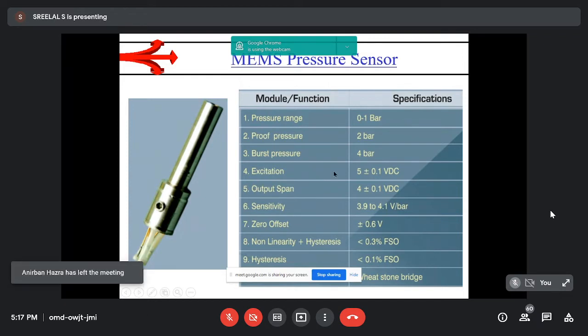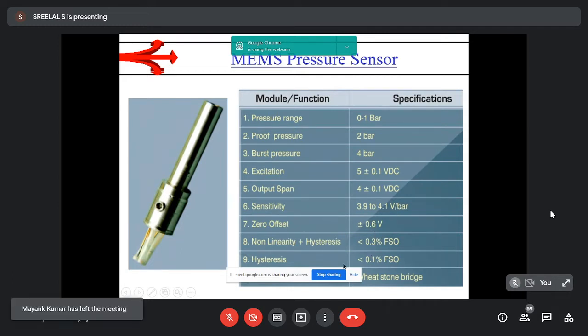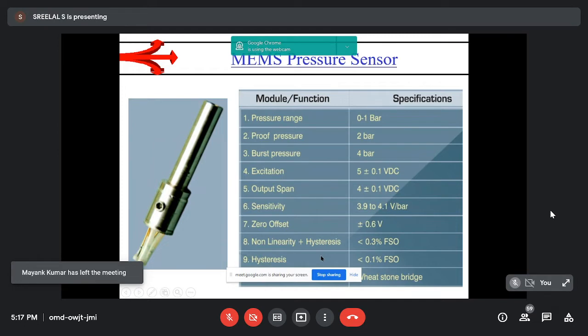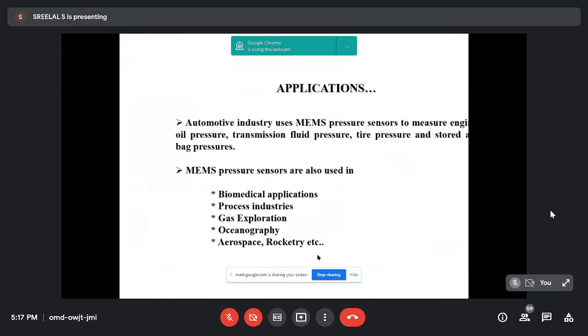It typically works with an excitation of 5 volt. It has an output span of 4 volt, and the sensitivity of the sensor is expressed as 3.9 to 4.1 volt per bar. That is, for 1 bar change, we get a nominal 4 volt output. It has a zero offset of 0.6 volt, and these are the accuracy figures of the sensor. It has a nonlinearity plus hysteresis figure less than 0.3 percent, and the hysteresis figure itself less than 0.1 percent. So these are the typical specifications of a MEMS sensor.